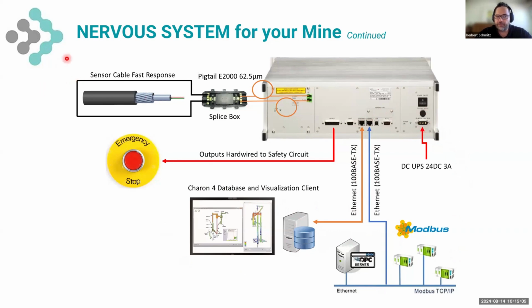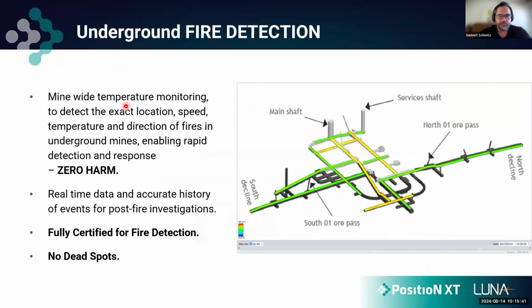On the sensor cable, if we have a fiber break, we know exactly where the cable is broken to go splice it back up. And being a normal single mode and multi-mode fiber optic cable, it's a normal fusion splice, nothing special in regards to the repairs. And if the fiber is broken, the controller ignores about 20 meters either side of the fiber break for bad reflections within the cable. This allows us to still have kilometers and kilometers of sensing and just splice it back up and the full system is operational.